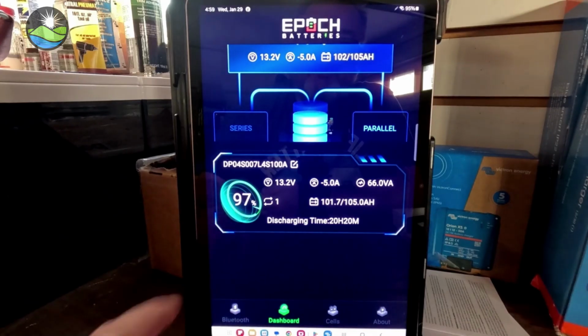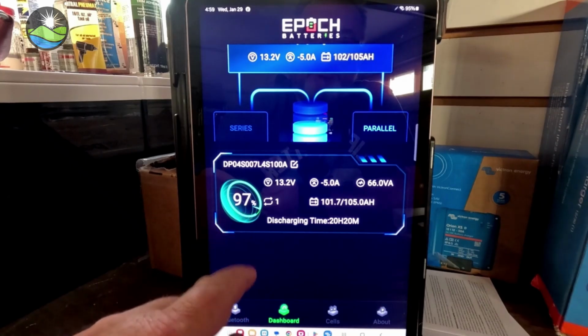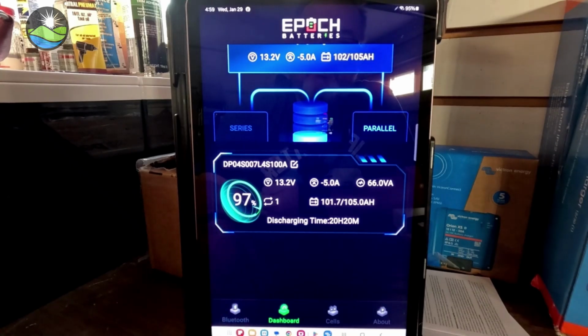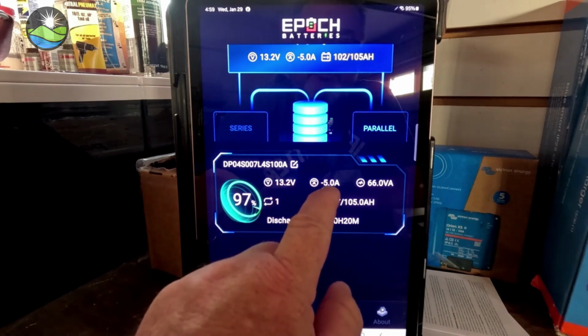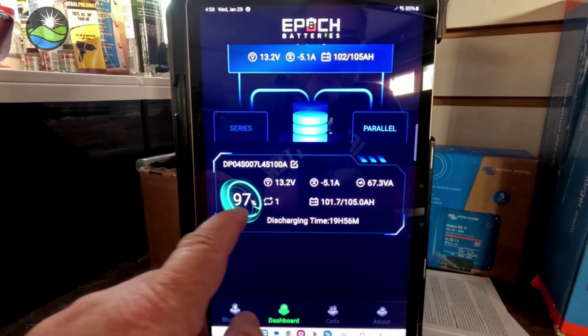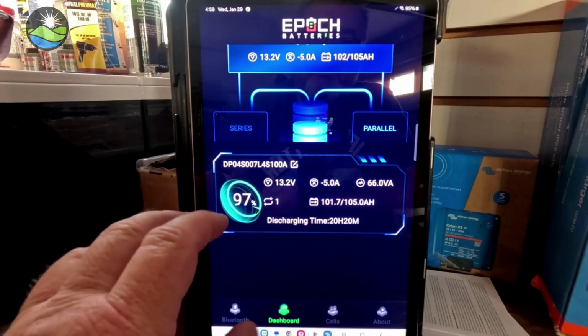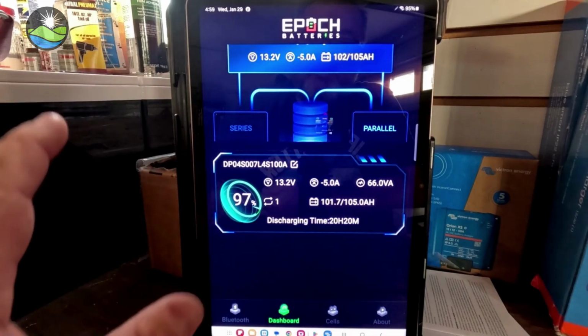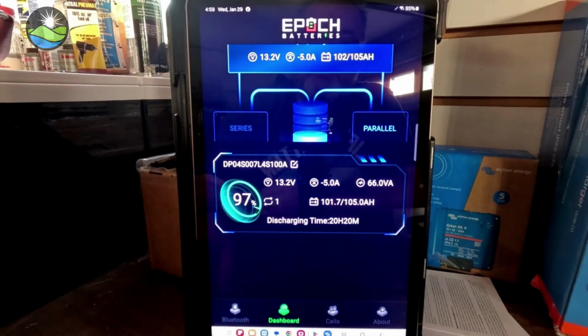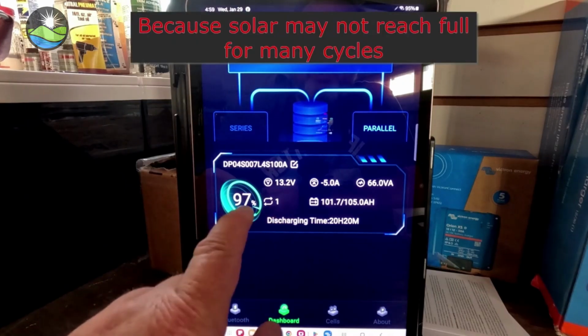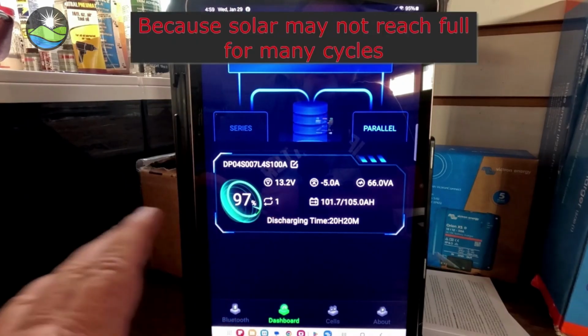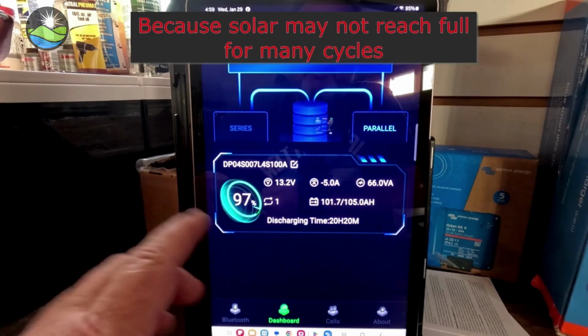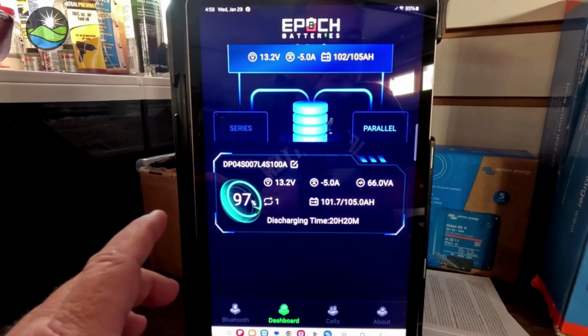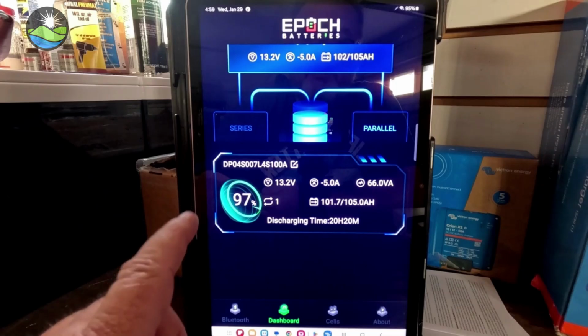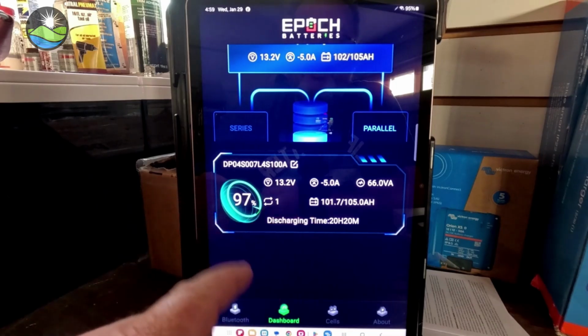Occasionally, if you're way out, you'll see this charge up and you're at 89 or 92%, but your voltage is at 14.2 and it's starting to get fully absorbed. Your amps are dropping. You'll see this go from 89 or 91 bang right to 100%. So that has reset the SOC. Generally speaking, if you're on solar, that is when you have a lot of problems with SOC drift. And this is true of any shunt. It doesn't matter if it's in the Epoch battery or even a Victron shunt, over time it can drift unless it gets back to the reset criteria, which is what I just described.